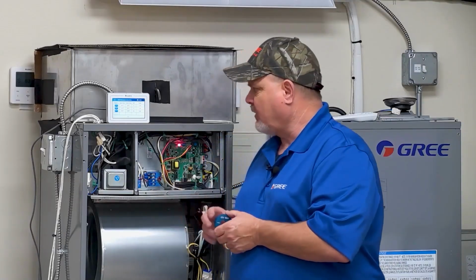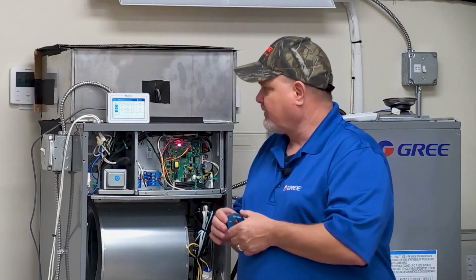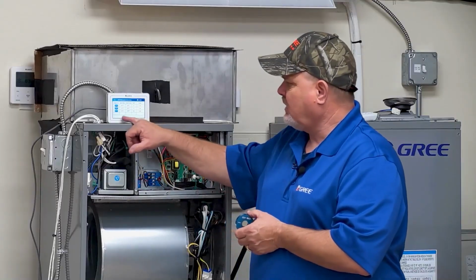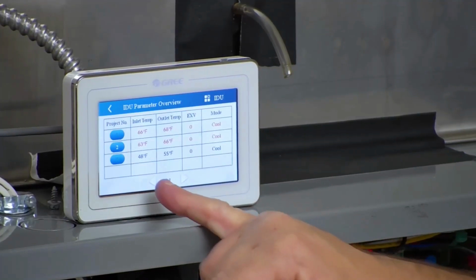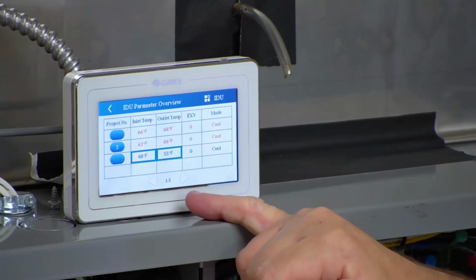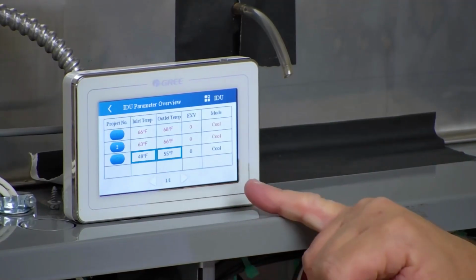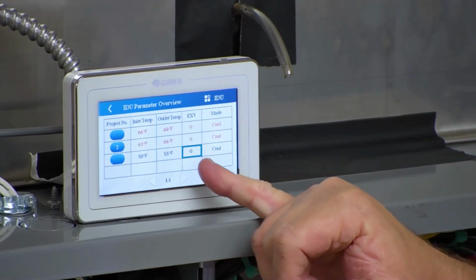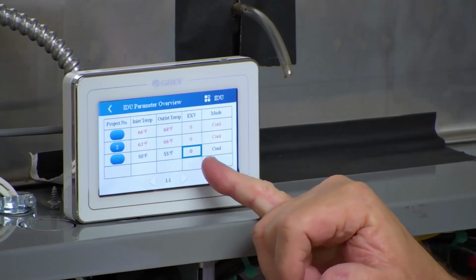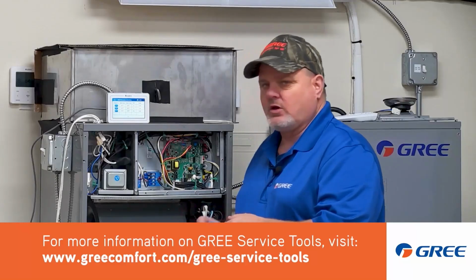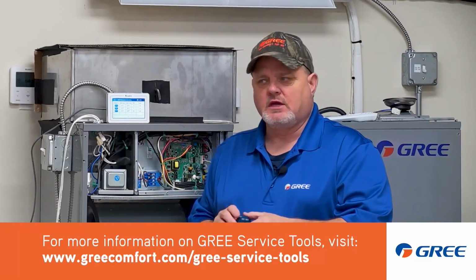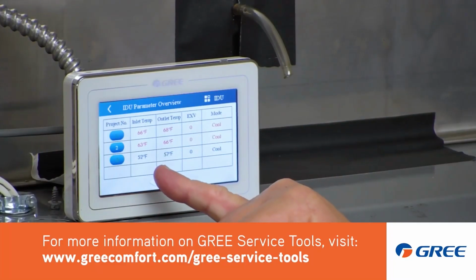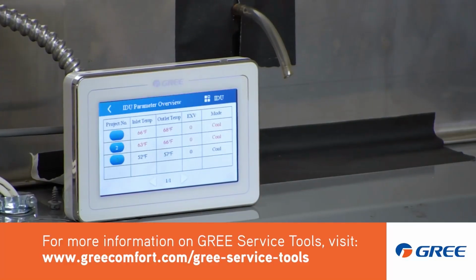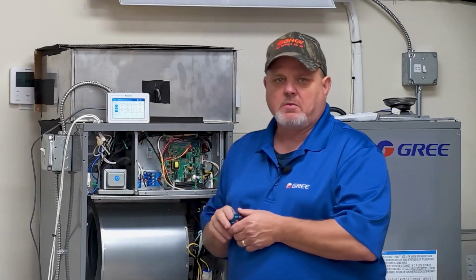So I unplugged that first. Now I'm going to give it a call for cooling, and you'll see on my service tool here, you have your inlet and outlet temperatures. As soon as it calls for cooling and the EEV goes open, you'll see this number change to a higher number, meaning the EEV is open. Then I'm going to go in there and manually open the EEV and show you the inlet temperature come down, then we'll manually close the EEV and you'll see that temperature go back up.